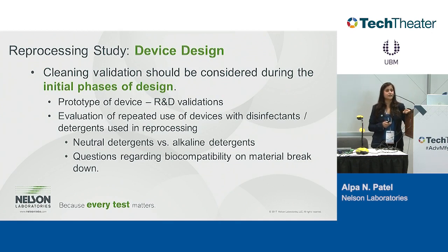Cleaning validation should be considered during the initial phases. Often we see that it comes at the end, like I said, but always test on a prototype. If you have a device design that you want to see if it's going to work well for cleaning validations, is it going to get the debris? Is it going to be hard to clean?